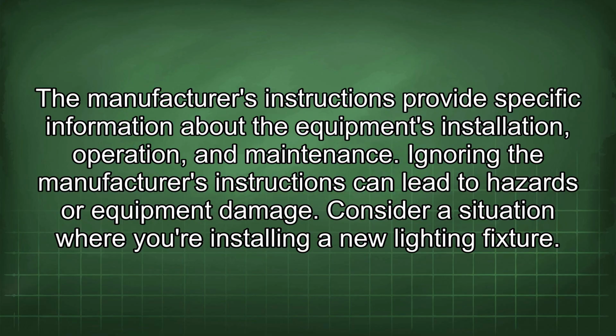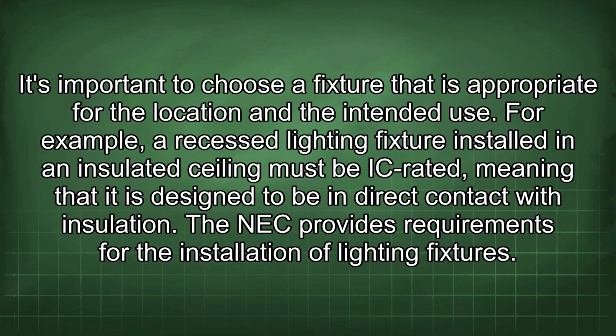Consider a situation where you're installing a new lighting fixture. It's important to choose a fixture that is appropriate for the location and the intended use. For example, a recessed lighting fixture installed in an insulated ceiling must be IC rated, meaning that it is designed to be in direct contact with insulation. The NEC provides requirements for the installation of lighting fixtures.